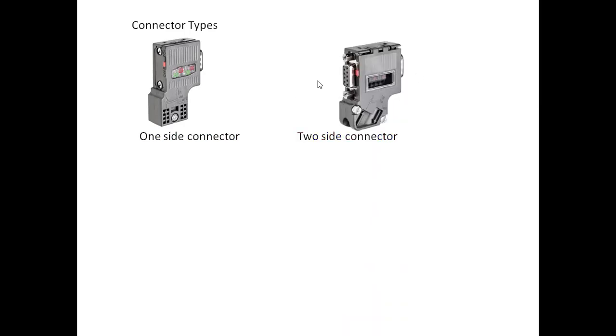Compared to RS-232 which has a maximum distance of only 50 meters, RS-485 has a much longer distance. Not only that, you can add multiple modules on RS-485, whereas on RS-232 you can add only one node — meaning only two devices can communicate with the main device. There are different connector types — Profibus connectors. One type has a connector on one side only, and another type has connectors on two sides — one at front and one at back — so you can extend the connection.